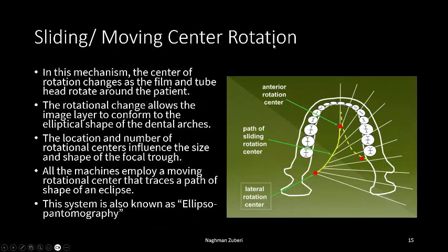In the sliding or moving center rotation, the center of rotation changes as the film and tube head rotate around the patient. This rotational change allows the image layer to conform to the elliptical shape of the dental arches. The location and number of rotational centers influence the size and shape of the focal trough. All modern machines employ a moving rotational center that traces a path in the shape of an ellipse — which is why it is also called ellipso-pantomography.